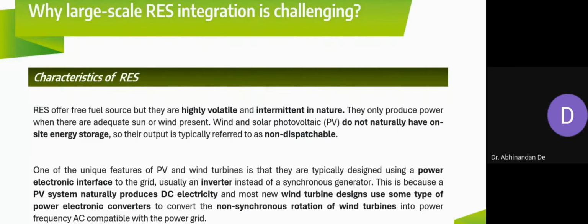So all we see is that they basically require some sort of inverter or converter, which are nothing but power electronic devices or interfaces, and they lack the inertia that a traditional synchronous generator normally has. So that is quite a challenge, right? Because this is one fundamental limitation of these inverter-based systems, which lack natural inertia. So nowadays we talk about synthetic inertia, and we try to simulate or synthesize inertia into these converters and inverters so that they can replicate the characteristic of a synchronous generator.